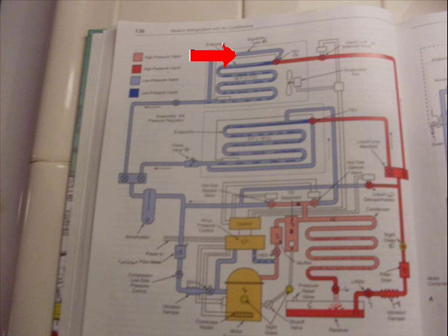You go through all these tubes and all these bends, this creates friction. And between the inlet and outlet, the pressure drop may be 3 or 4 pounds through the evaporator. Now, thermostatic expansion valves, you will learn, work on low side pressure and the temperature of the suction line on the outlet of the evaporator. If the low side pressure on the outlet is different than the low side pressure on the inlet, it will throw the valve off and the valve will starve the evaporator and efficiency will go down.